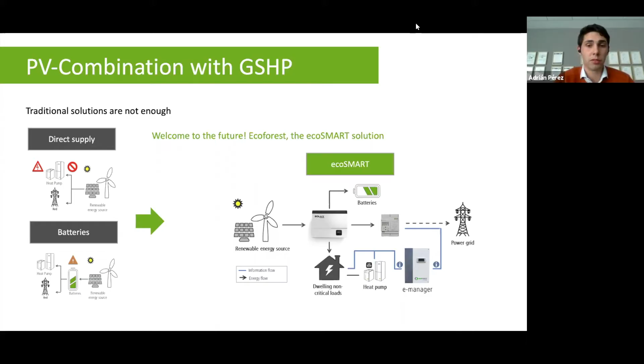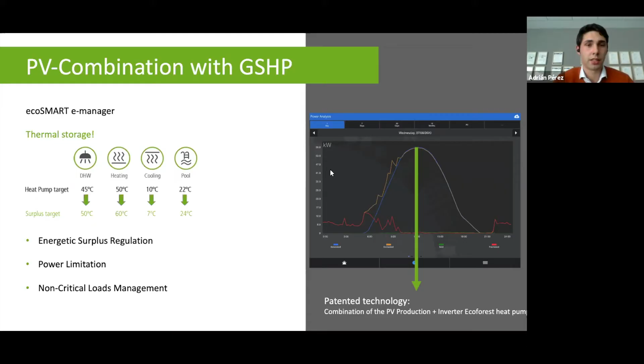So we can do thermal storage in domestic hot water, heating, cooling, or even the pool. This product has other features like power limitation and non-critical load management, but what we have patented is this curve. In the graph, blue is what the PV is generating and orange is what the heat pump is consuming. When the PV is enough for our heat pump, the heat pump totally adapts to this production, thanks to the combination of our heat pumps with our software and inverter technology. This is patented by Ecoforest.